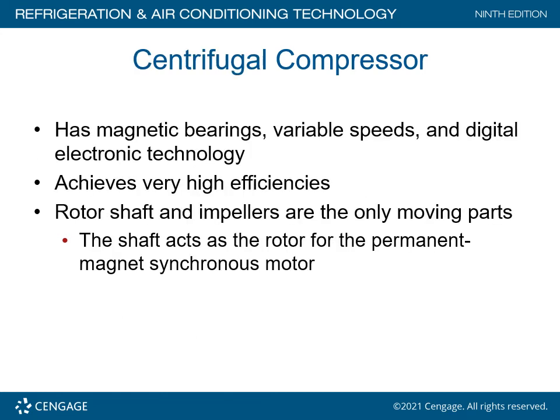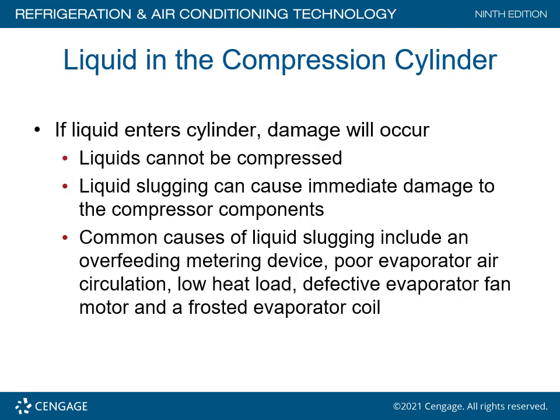Centrifugal compressors have magnetic bearings, variable speeds, and digital electronic technology, achieving very high efficiencies. The rotor shaft and impellers are the only moving parts. The shaft acts as the rotor for the permanent magnet synchronous motor. These are large units — you typically won't find a centrifugal compressor under 150 tons, and you need a lot of specialized equipment to work on them.